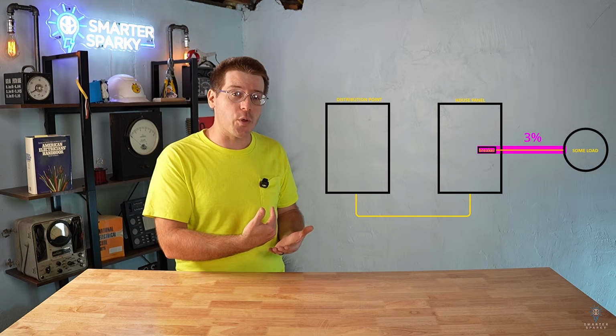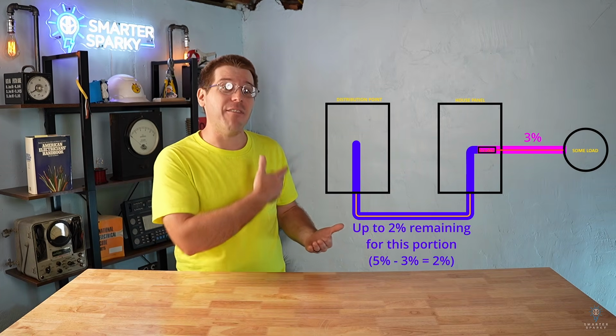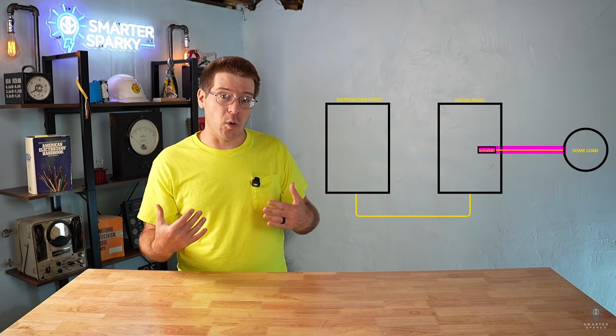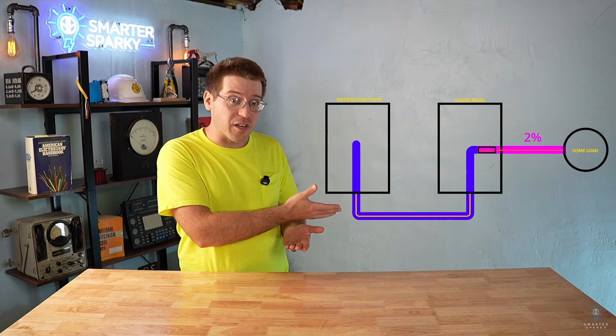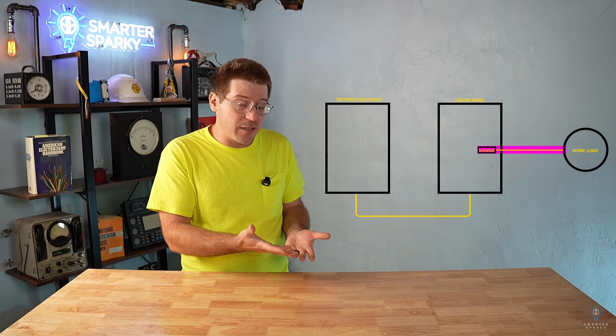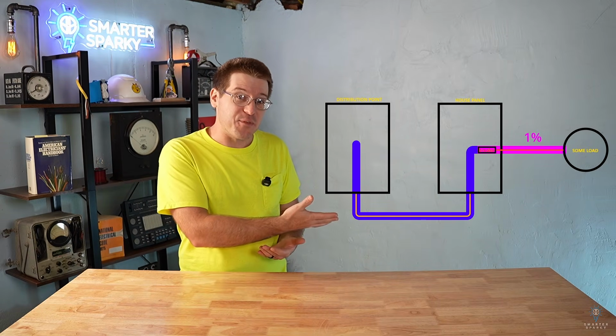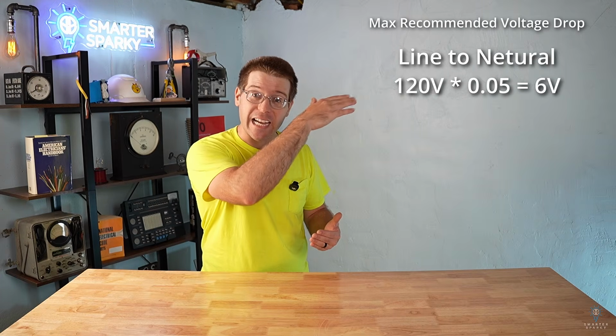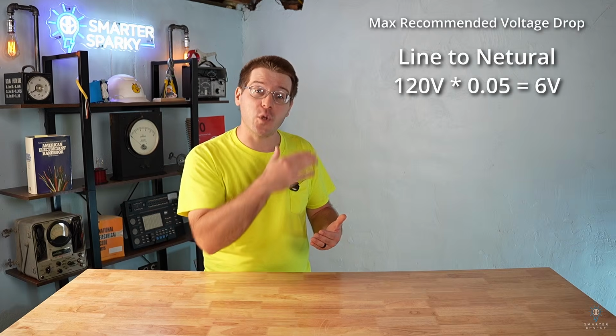So if the branch circuit has the full 3% voltage drop, that means the feeder could have up to 2% voltage drop. But if the branch circuit only has a 2% voltage drop, that means the feeder could have 3% voltage drop. And if the branch circuit only has 1% voltage drop, that means the feeder could have 4% voltage drop. Because we're just doing some rough troubleshooting here, I'm gonna pretend the branch circuit voltage drop is negligible, 0%. That means we should see a maximum of 5% voltage drop at the lugs in this panel. That is gonna translate into an absolute maximum of 6 volts line to neutral for voltage drop, and a maximum of 12 volts from line to line. Now, realistically, we should probably have no more than 2% voltage drop at these lugs in this panel.